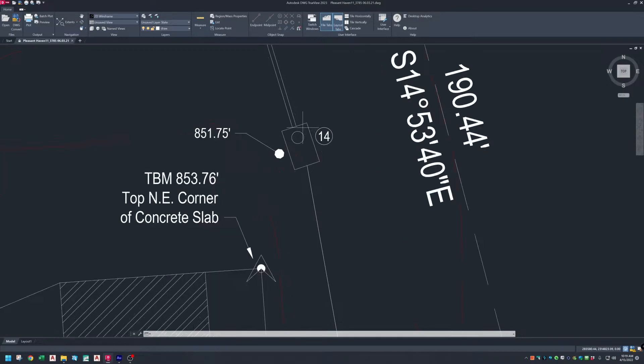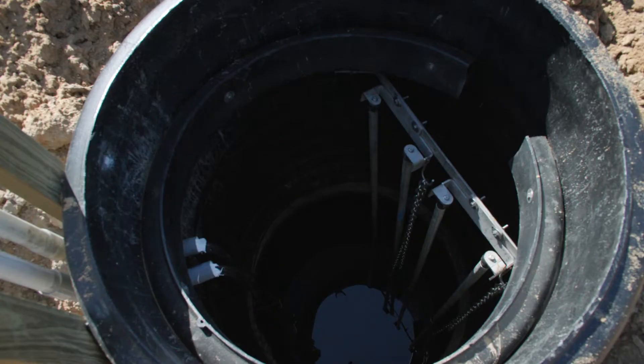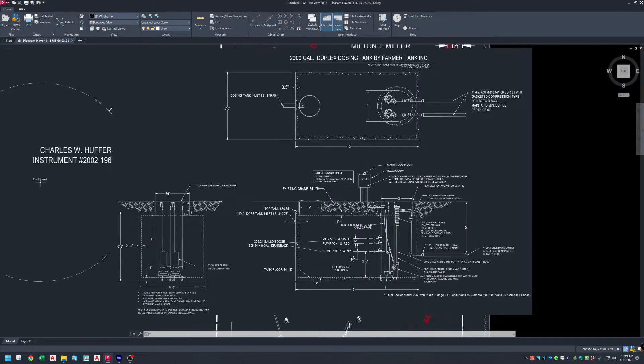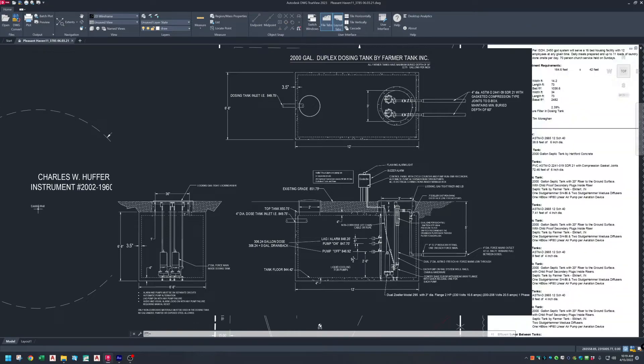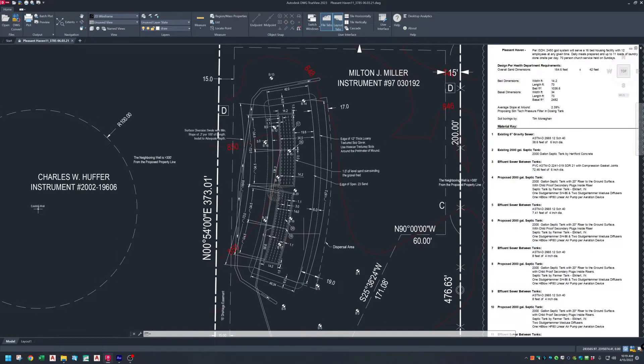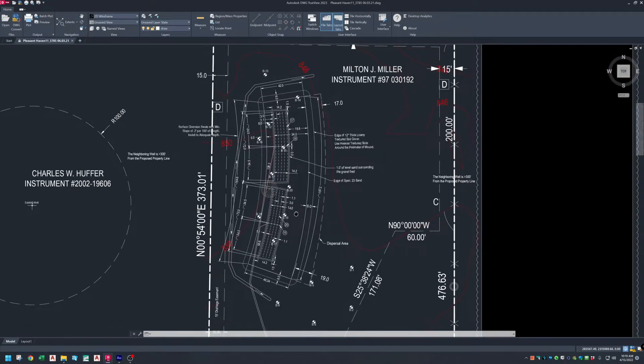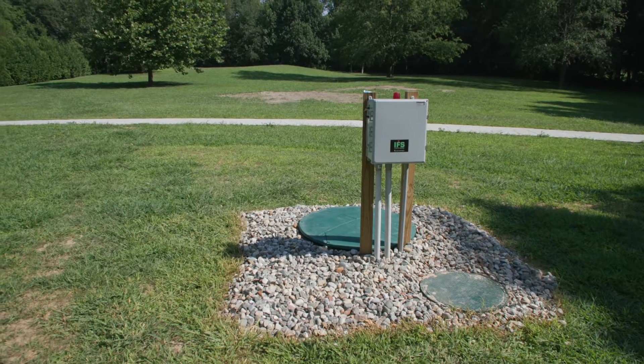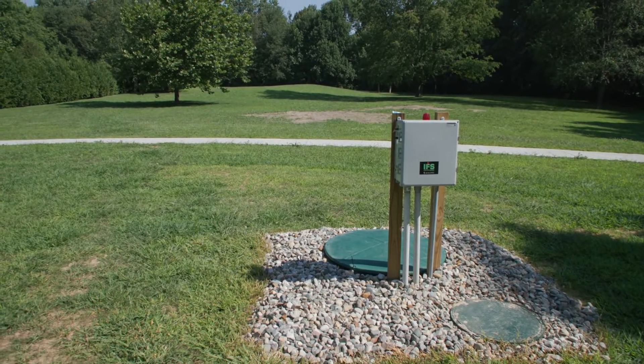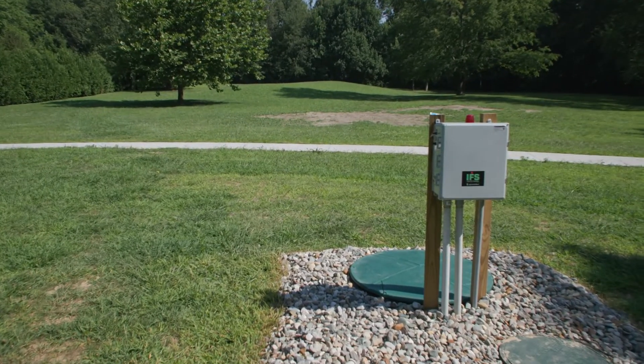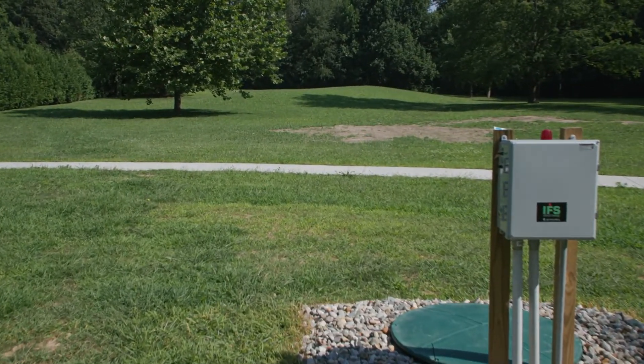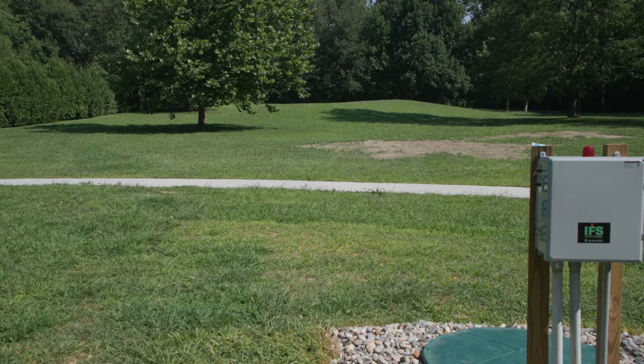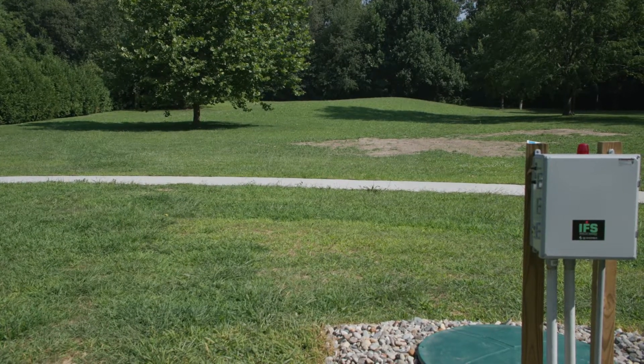The treated water flows to a duplex dosing tank where it's pumped to a 2,400 square foot mound system using dual Zoeller model 295 pumps that each deliver 153.6 gallons per minute at a total design head of 22.58 feet.